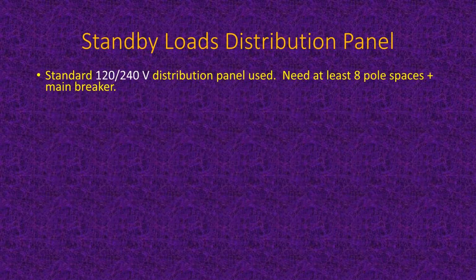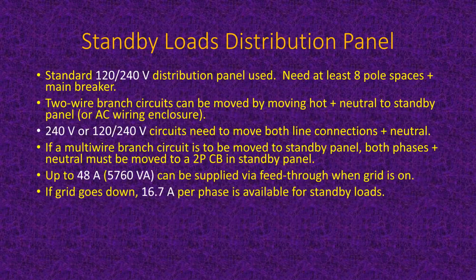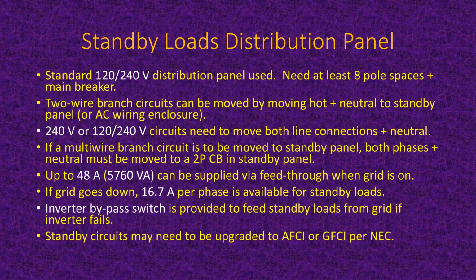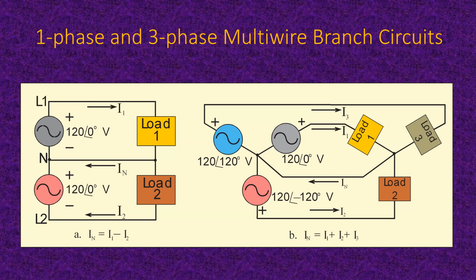So distribution panel for the standby loads, again, it's just going to have to be big enough to hold the loads. Pretty straightforward. The important thing is if you take some loads out of one panel to put in another, if you have any multi-wire branch circuits, then you've got to make sure you move both circuit breakers. Say you've got 2 circuit breakers side by side, one does the master bedroom, one does the front bedroom. If you're going to power up the master bedroom after a hurricane, then you've got to power up that front bedroom too, because you have to pull both sides of that neutral. Otherwise, the neutral is going to be overloaded.